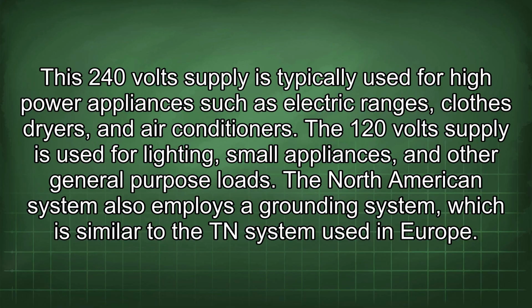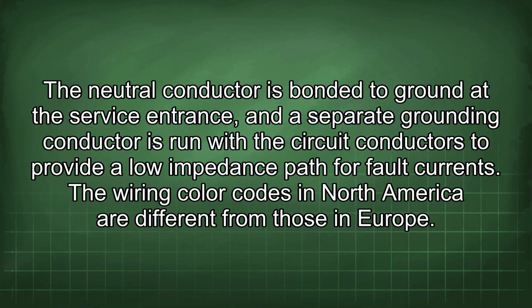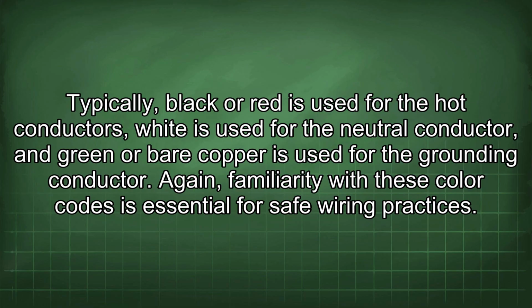The North American system also employs a grounding system, which is similar to the TN system used in Europe. The neutral conductor is bonded to ground at the service entrance, and a separate grounding conductor is run with the circuit conductors to provide a low impedance path for fault currents. The wiring color codes in North America are different from those in Europe. Typically, black or red is used for the hot conductors, white is used for the neutral conductor, and green or bare copper is used for the grounding conductor. Again, familiarity with these color codes is essential for safe wiring practices.